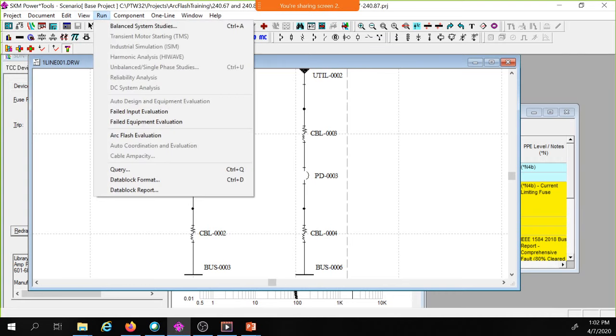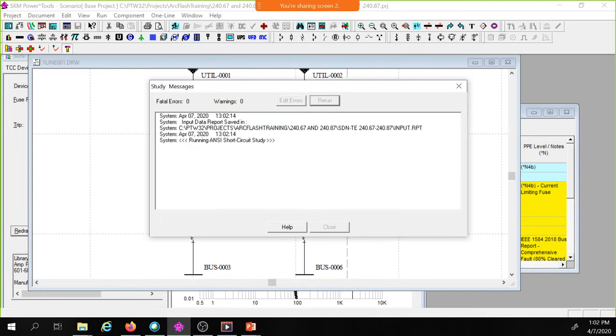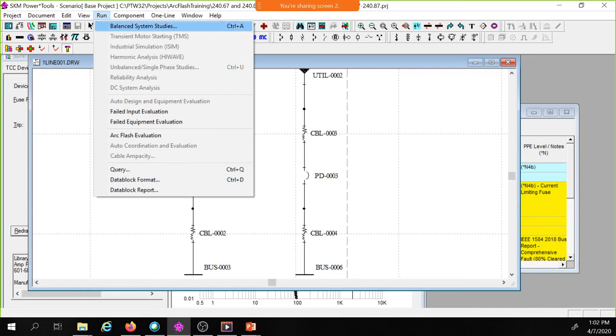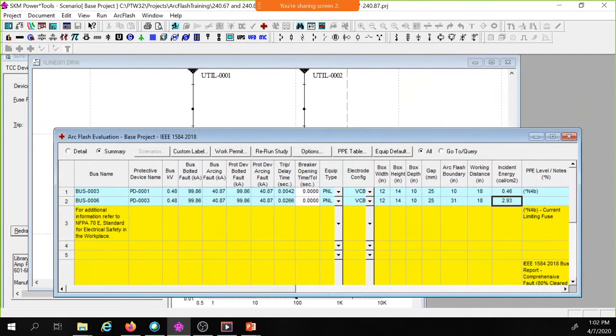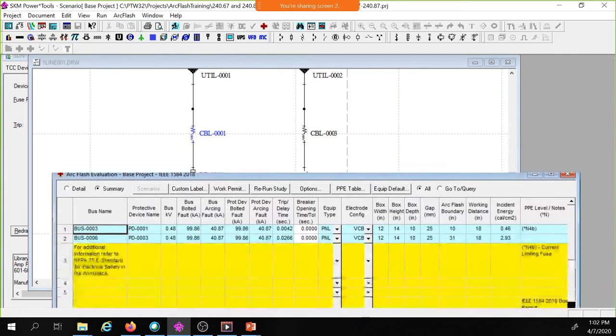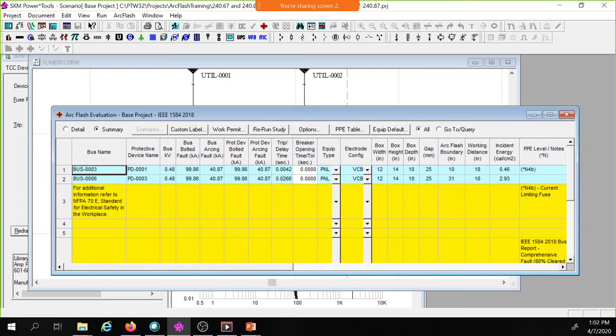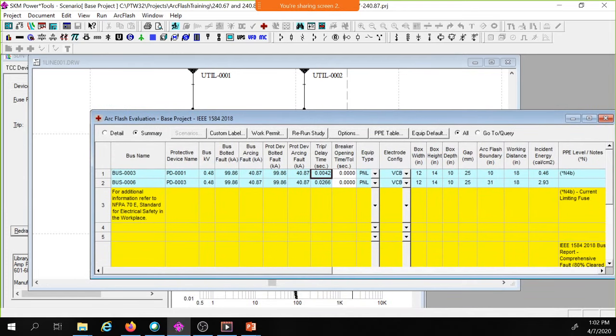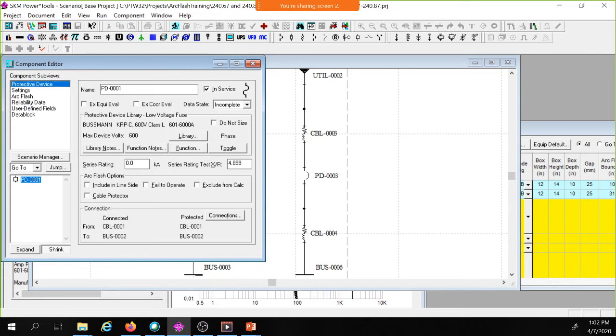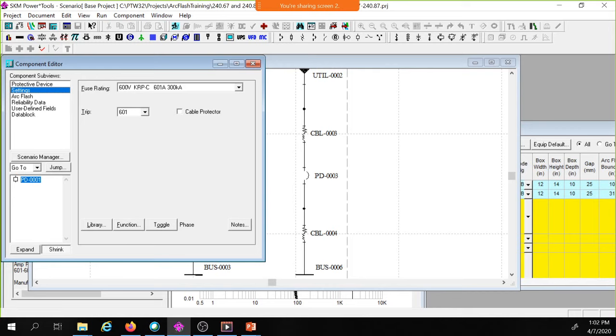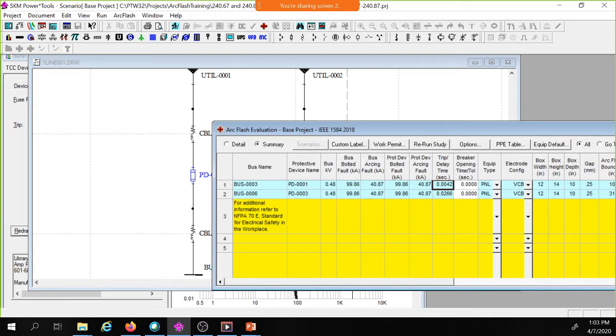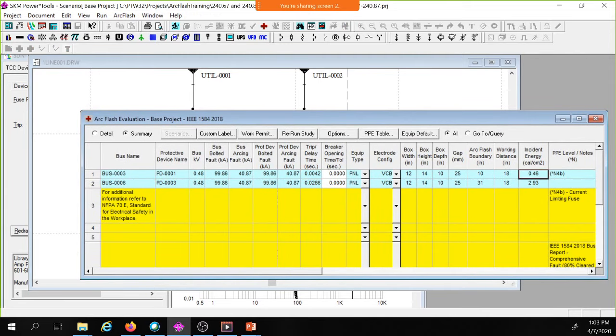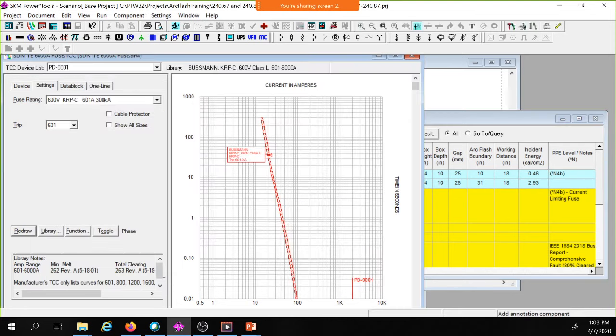If I run my balanced system study, short circuit, I run my calculation, and then I'm going to run an arc flash evaluation. So here are both of these scenarios. My fuse scenario is bus 3, and bus 6 is the breaker scenario. I have an available short circuit current passing through that fuse of 99,860 amps, and my arcing current is 40,870. This tells me the clearing time of the fuse I have in place, which I'm not sure of the size. Let's take a look. This is a Bussmann KRP fuse, which is a 601 amp fuse. We're going to change that shortly, and I'll show you what it does to the incident energy. My incident energy is 0.46 calories. My clearing time is 0.0042. So here's what I'm going to do. That's my fuse curve.